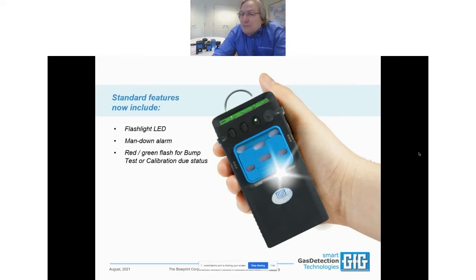But you can also set the instrument up with a panic button feature. So if you want to manually sound the alarm for some reason, you want to get everybody's attention, instead of using the flashlight as a flashlight, we set it up to be used as a panic button. You push the button and the painfully bright flashlight LED starts flashing. The painfully loud audible alarm starts howling. The LEDs flash. It's going to do everything it possibly can do to get everyone nearby's attention. And of course, if you have a wirelessly enabled version of the instrument, that change in status and the panic alarm will be communicated to the remote TeamLink server or to a remote base station.